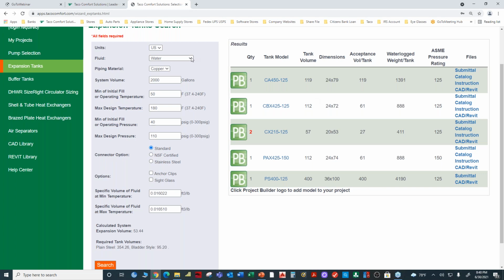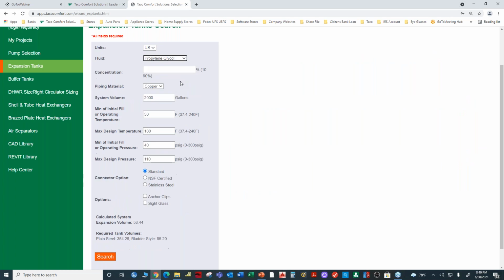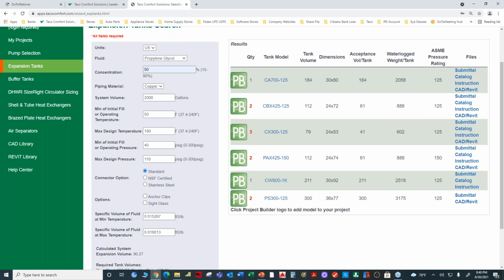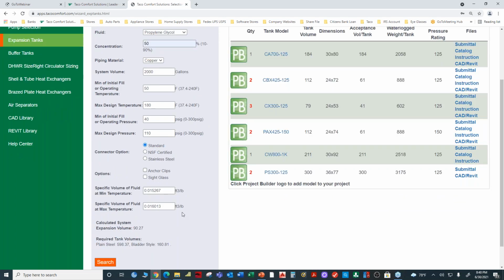So we're going to change the fluid from water to propylene glycol, and then let's put in 50% - that's 50% propylene glycol - and click on search. Look what happens to the expansion volume: it went from 53.44 gallons to 90.27 gallons.